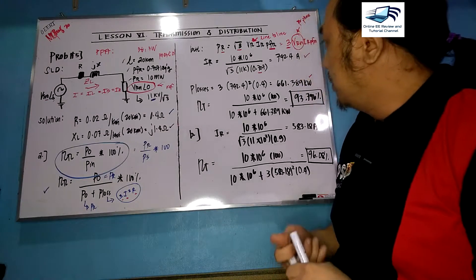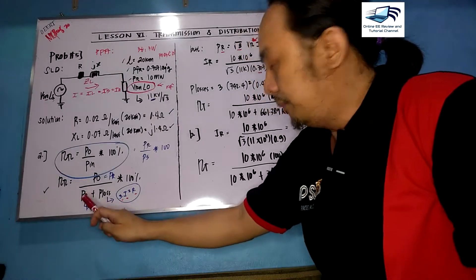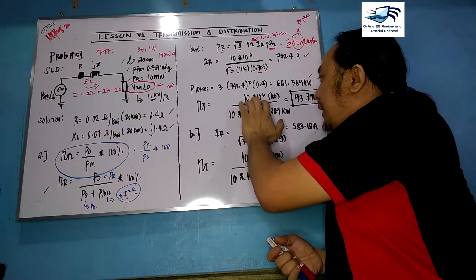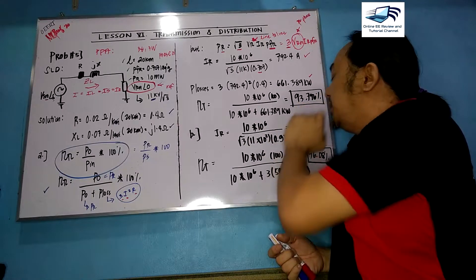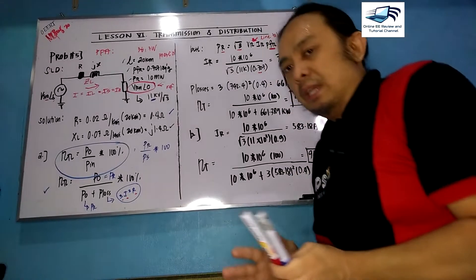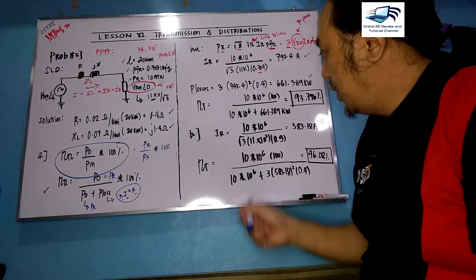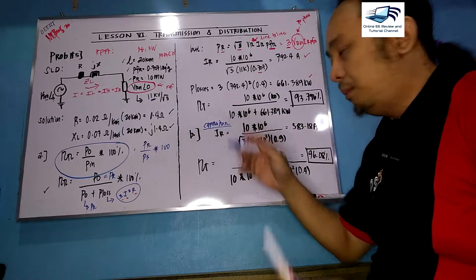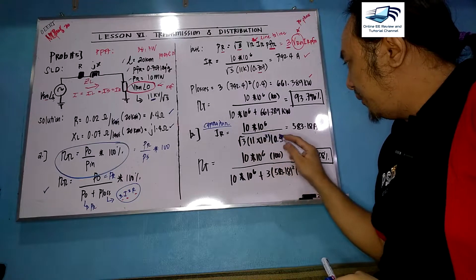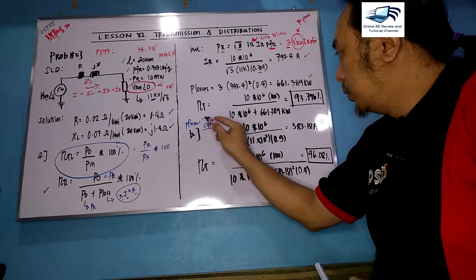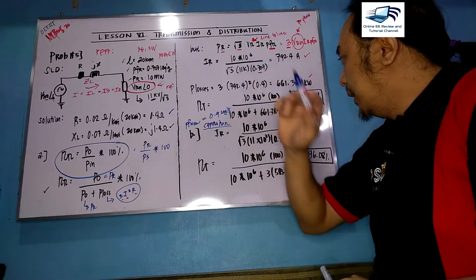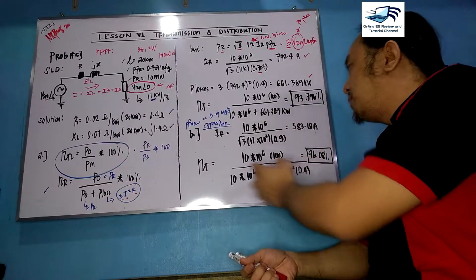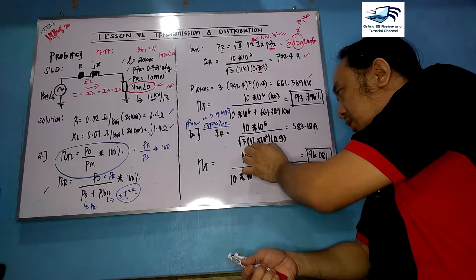Substituting all computed parameters into the efficiency equation: 10 megawatts over (10 megawatts plus 661.389 kW), multiplied by 100, the answer is 93.79 percent. Now the problem requires a second scenario: if a synchronous capacitor or condenser is added, raising the power factor to 0.9 lagging, what will happen to the efficiency? We apply the same approach with the same 10 megawatts and 11 kV receiving end voltage but with the new power factor.